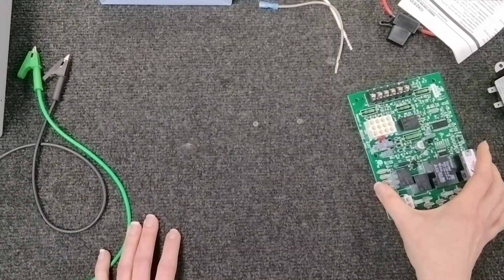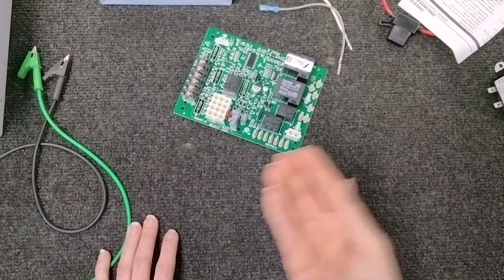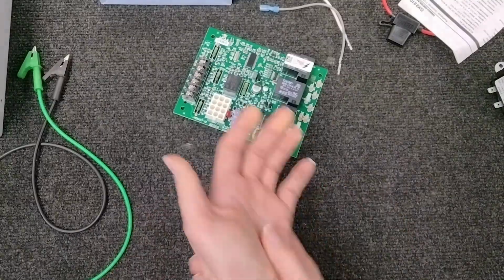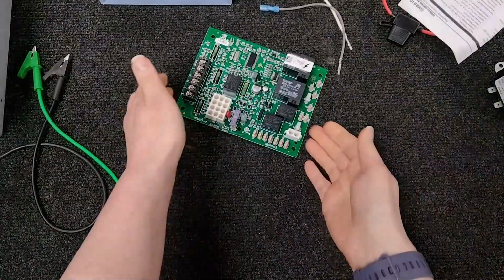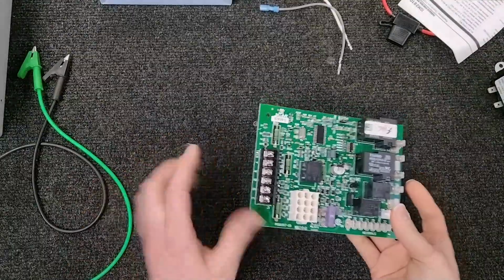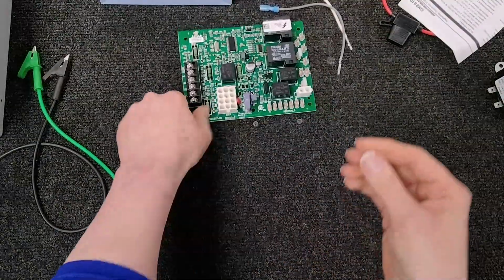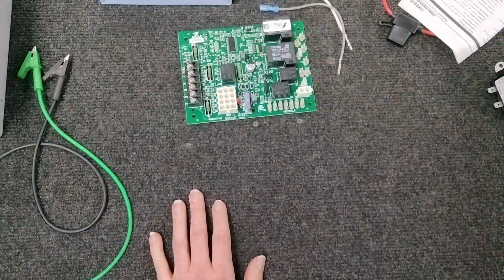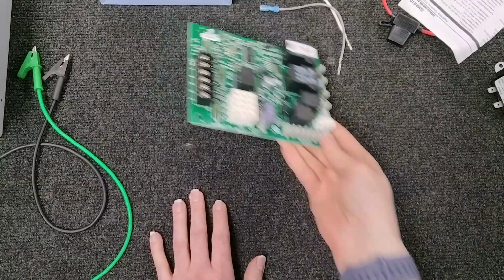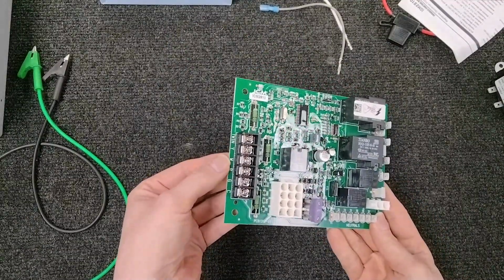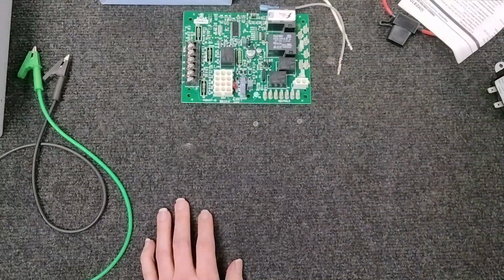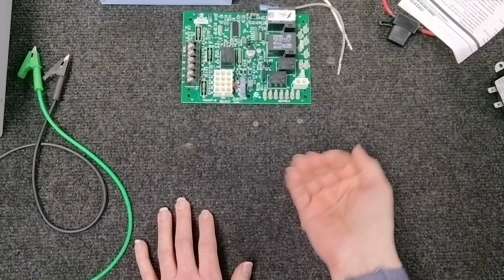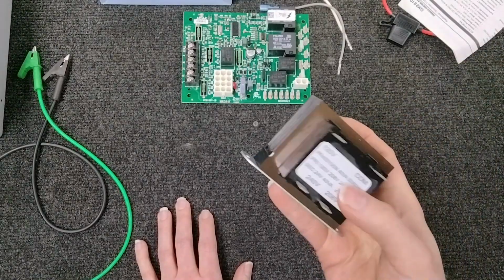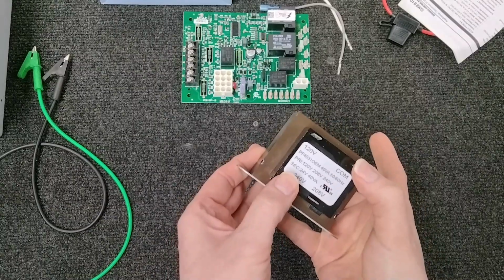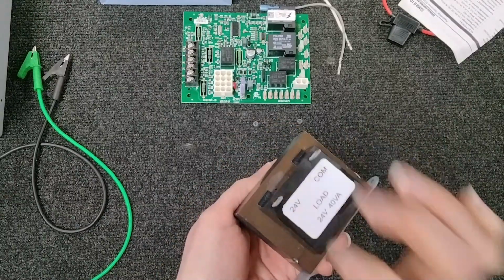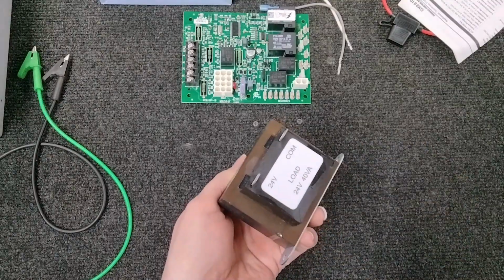Now with air handlers, the newer ones are going to have those fan control boards that'll connect and whatnot, just like here. Obviously it's going to be different because it's going to go directly to the unit instead of being on this board. You'll see all your thermostat wires coming up to the unit. That doesn't change. You need to check between your R and your W and make sure that you are getting the call from the thermostat and that there is power coming into your unit, as well as checking your transformer between your 240 and your common, and then of course making sure that you are getting that 24 volts out.